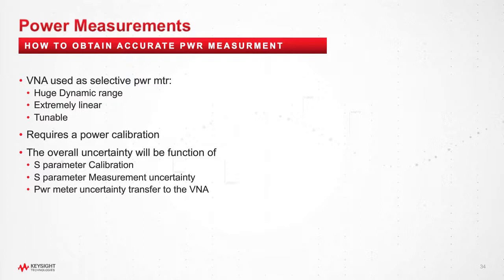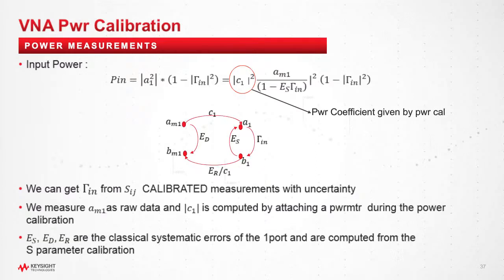So this is the equation, and this C1 is the coefficient I talked to you about before. In order to compute C1, you have to make an absolute power measurement, which means that rather than your device here, you have to put your power meter. The power meter reading is known now, a_m obviously is known, and all the rest become known. And what you get is C1. Now, clearly, if you use the METAS uncertainty library to compute the uncertainty on the power in, it is straightforward, and that's exactly what we have done. So this is given by the power cal, and this is an example of the uncertainty of the power given by a VNA.